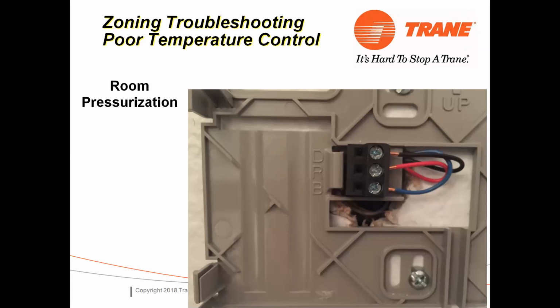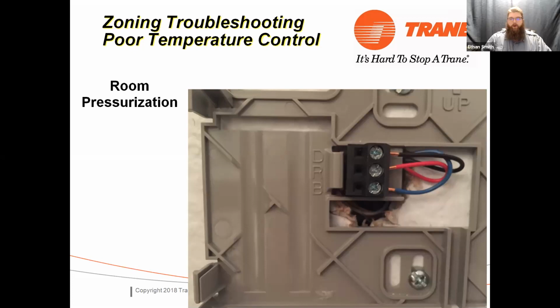Open area behind the wall? You have an open air passage through the thermostat. So if your room gets pressurized a little bit, either positively or negatively, it's going to either pull air out of the wall or push air through the stat into the wall, most likely out of the wall. We generally have negative pressure zones rather than positive pressure zones. And so we are going to bias the sensor as that air flows through that sub base through the thermostat, and it's going to cause that sensor to read improperly.